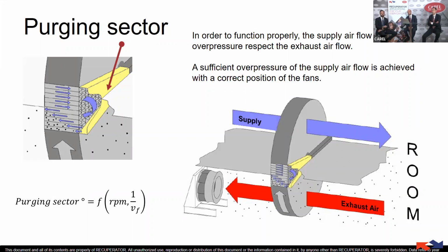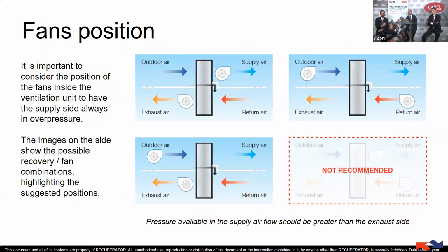That means it should be at the outlet of the supply side, and also opened in the same direction as the rotation. It should also be well designed, because it depends on the revolutions per minute of the rotor and on the velocity of the front of the supply air. In addition, to work properly, the supply side needs to be in overpressure. The supply side in overpressure is also really important to avoid the leakage that we can have with the rotary heat exchanger being transformed into contamination.